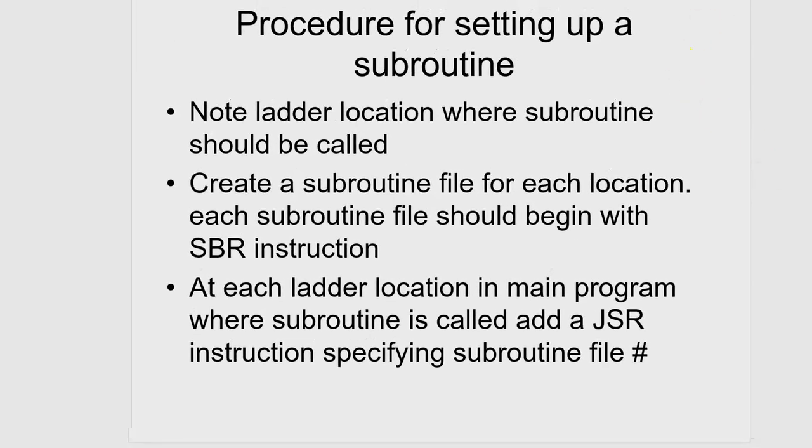So I have that note ladder location where the subroutine should be called. That is where you're going to have the jump to subroutine start. You create a subroutine file for each location. Each subroutine file should begin with the subroutine instruction. Actually, it won't work if you don't do that.